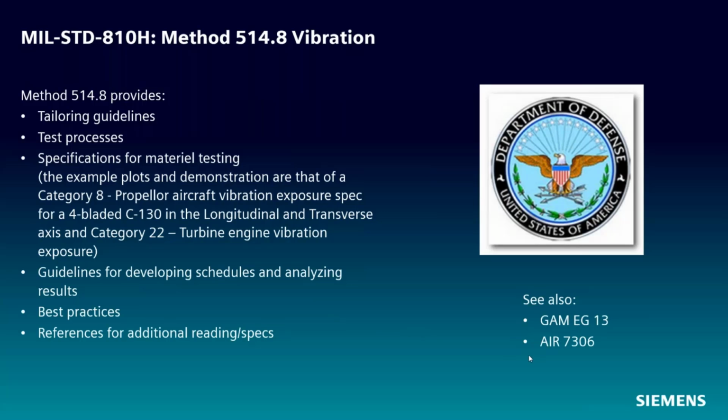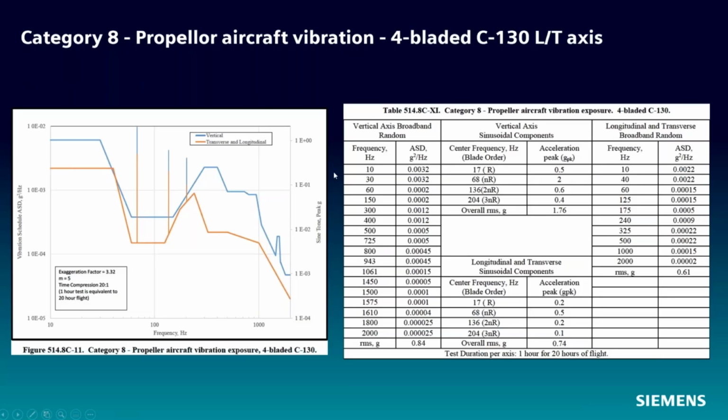You can also see some mixed mode or combined mode specifications in other standards. Feel free to look those up as well. But our main go-to in the US at least is typically this MIL standard 810, and we're at revision H right now. This is one test that we're going to run now.